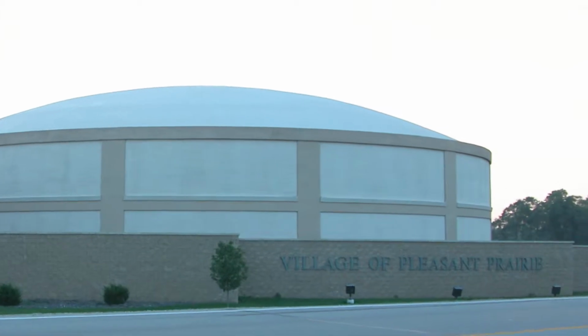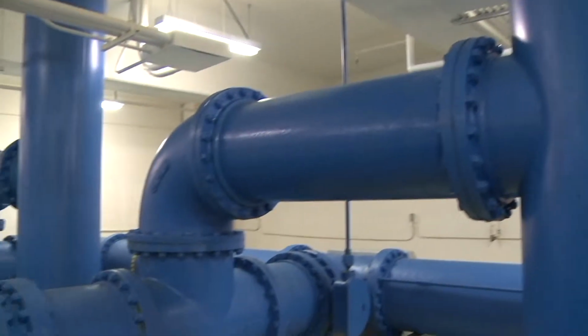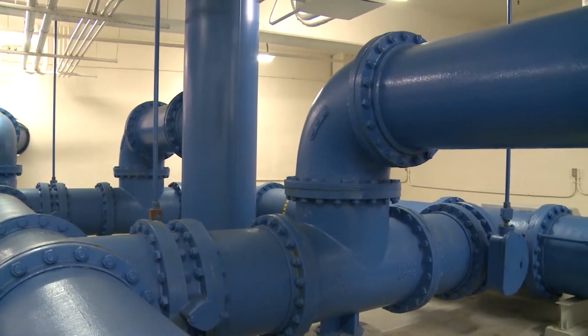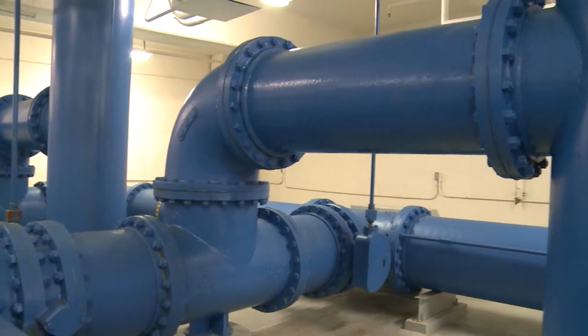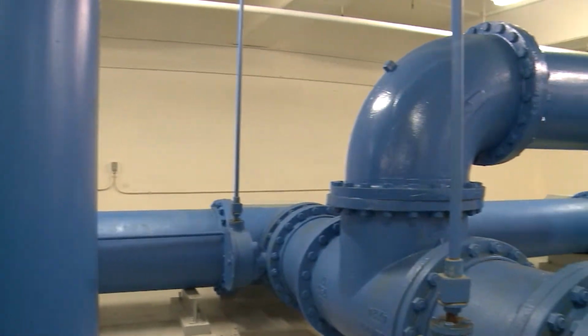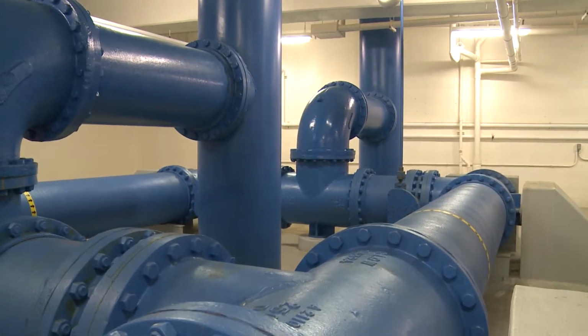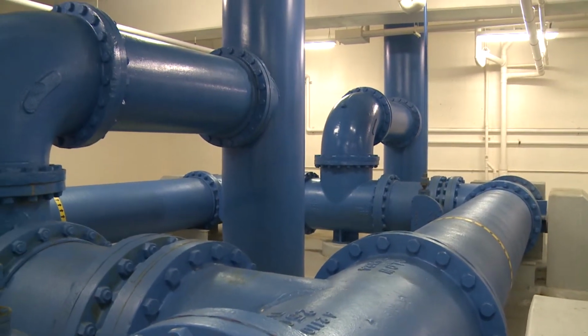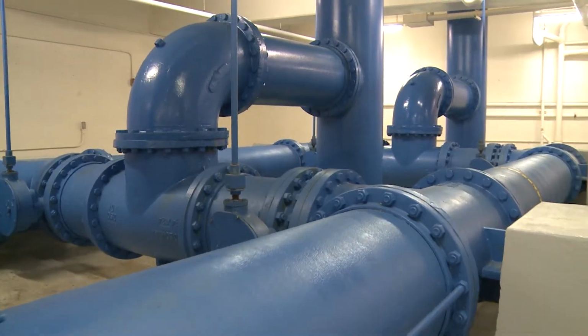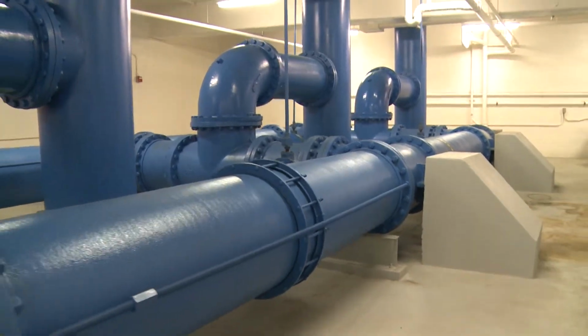Large pumps at the Sheridan Road booster station then send the water through transmission lines to a second reservoir and booster station and 4 elevated water towers located throughout the village. On any given day, an average of 9.2 million gallons of water are stored within the village reservoirs and tanks: 2.25 million gallons for an average day's use at homes and businesses, and close to 7 million gallons in reserve for fighting any potential fires and other potential needs.